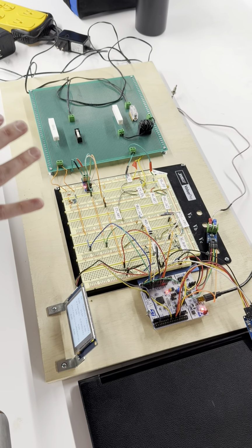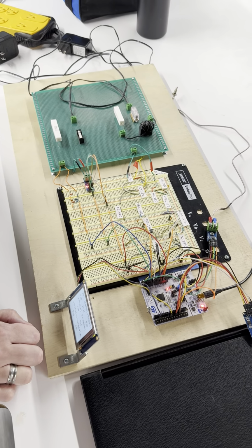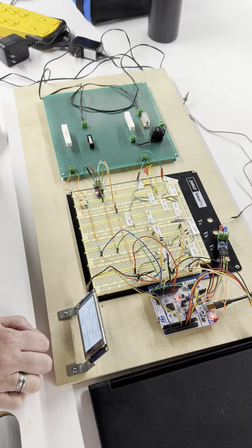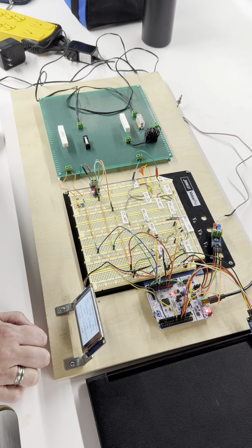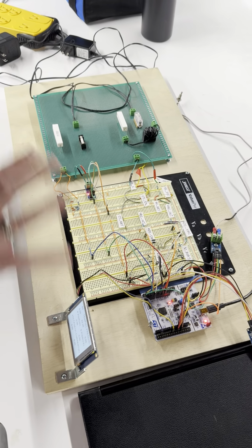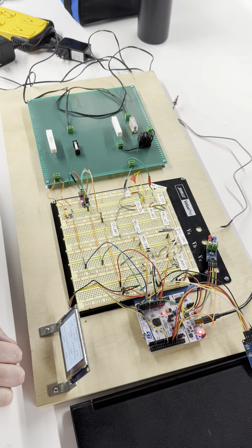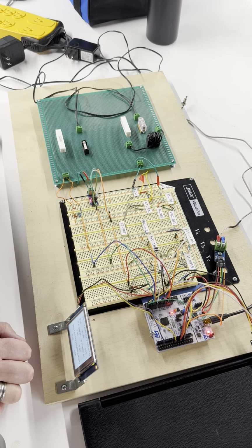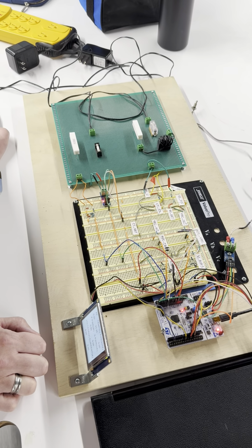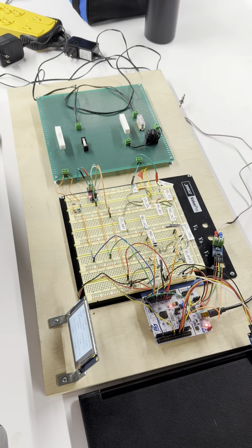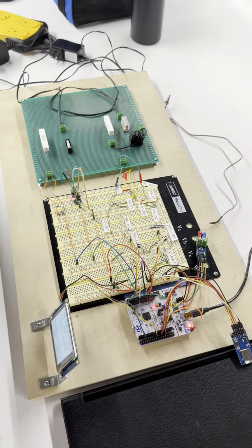The way that we actually compute frequency is through something called a zero crossing detector method, using hysteresis to reject noise at the bias point. Power is all computed. Real power is essentially the average of voltage times current. Apparent power is VRMS times IRMS, and then power factor is just real over apparent.